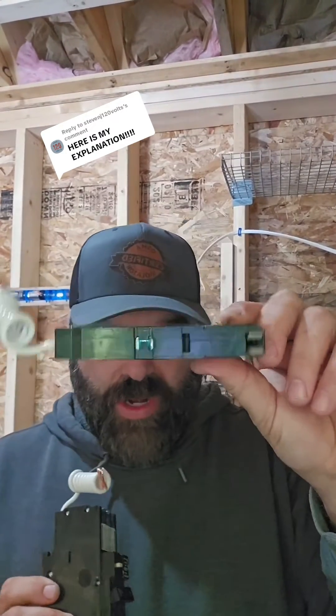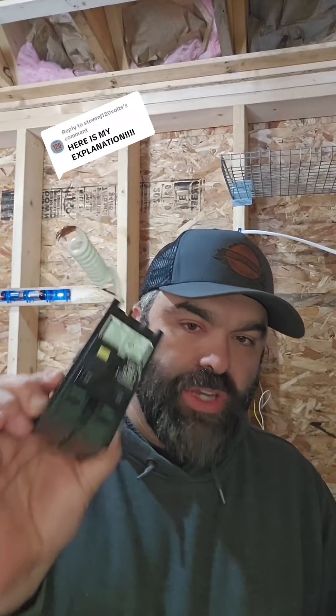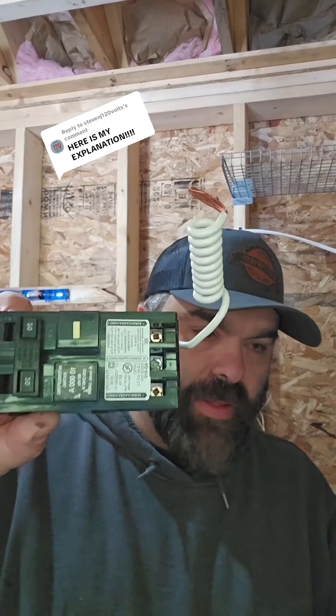Now, if it was a single breaker and it was new, there's a chance it could be a GFI or an arc fault. But a two-pole breaker that old is most certainly a GFI breaker. And that little pigtail is the sign.